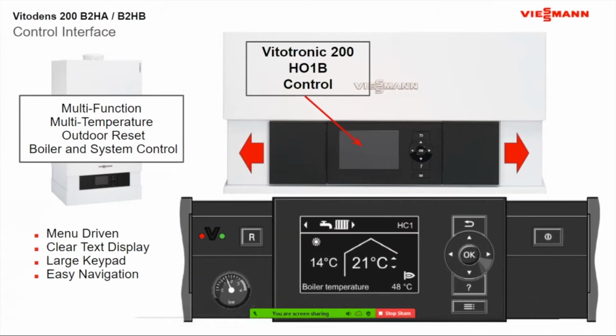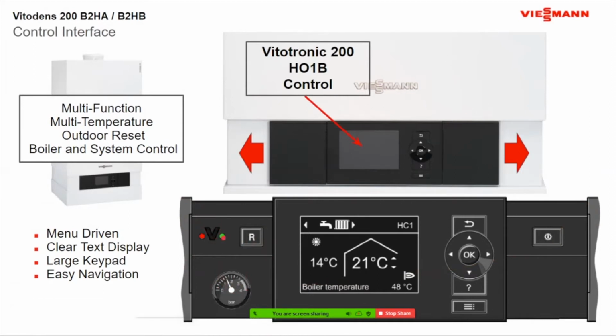If you haven't worked on this boiler before, and believe it or not, I have had these calls, where is your on and off button for this boiler? You have to slide these little doors here, left and right, to the sides. On the left-hand side is your reset button, your pressure gauge, and then your Optolink here, where this V is. We actually sell a device that you can plug into the V where the homeowner can have some type of monitoring of their boiler, whether it be a fault notification, or if they want to do temperature changes, or say they want to do vacation mode. We'll talk about that as well coming up. Red, if it's just blinking red there, you have a fault. Green's all good. We're on the way.